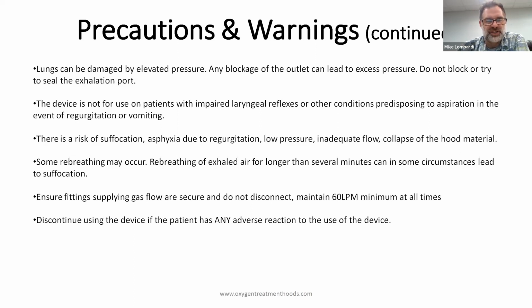And I guess, as I mentioned, there is a risk of suffocation if the patient were left alone and there was significant failure of the overall system. You need to be aware of that. And some rebreathing may occur. So that emphasizes the need to have a high flow at all times. This is a high flow situation, high flow device generally, but it's very important to maintain that 60 liters per minute flow at a minimum. And then, as with all medical devices, we'd want to discontinue using the device if the patient had any adverse reaction.